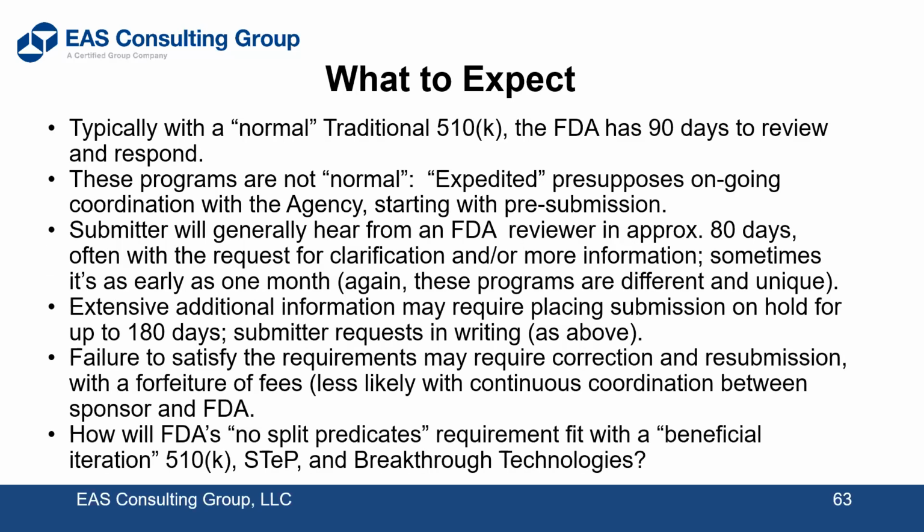As I mentioned, the FDA says 90 days to review, but it actually drags out to about 120 in most cases. Sometimes, rarely, it comes in under that, and it can exceed that as well. And if you have clinicals, it's longer than that as well. You can't split predicates, the last bullet point down here. You used to be able to do that: use several different predicate devices to combine technologies into one device from two separate predicates. Not a combination product.